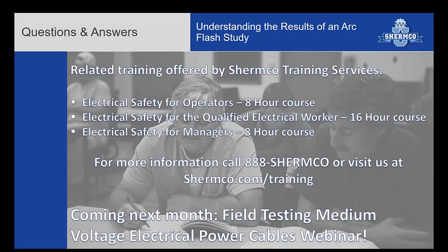Yeah, I think unfortunately the answer is yes. Just because it can be so different, like I'm saying, with just a different size utility, on each one. One might be a 1,000 kVA transformer feeding it, and the other one might be 500 kVA. It can be so unique that I think the safest and the most correct answer is you must have a study done on each one. I would agree with that.